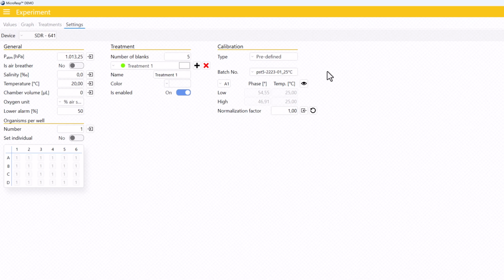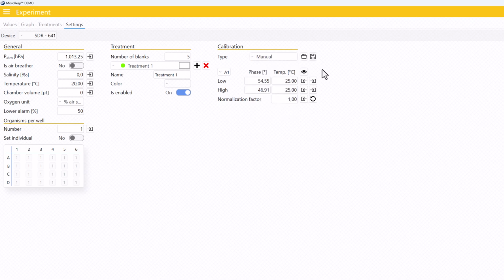Another reason is that optical oxygen sensors are very temperature sensitive, so it's important to keep the temperature of the sample and glass plate constant at ±0.5 degrees Celsius and to calibrate the sensors at a temperature within ±1.5 degrees Celsius of the experimental temperature. And as you can see from the file names in the list, these batch calibration files were calibrated at just two different temperatures, 10 and 25 degrees Celsius. The manual or 2-point calibration option calibrates the oxygen sensor spots at two different air saturation levels, 0% and 100%.